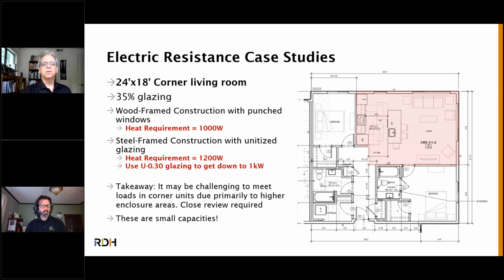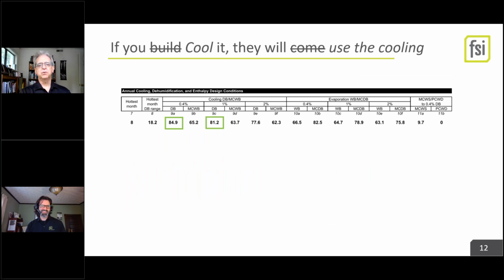So with that, Mr. Roush has something to say about cooling. This is a little bit of a repeat on the front, but our design temperature, this is Seattle, says 85 degrees. And yes, there are a great many days over 90 at this point, and we don't do a lot of projects without cooling anymore. But at 85 degrees, that's 35 hours a year that you would expect at that 0.4% percentile. I think we're actually higher than that now. And this June 1st, a mere week ago, was a rarity. It was up with 4% of the past historical record for hitting over 80 degrees on June 1st.